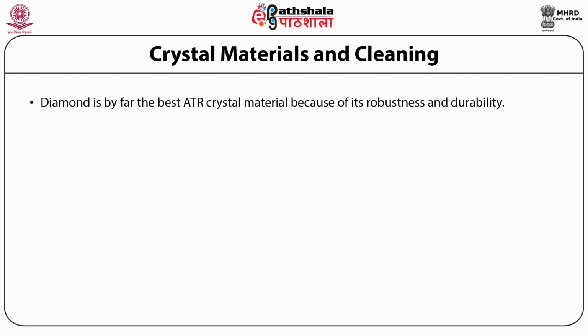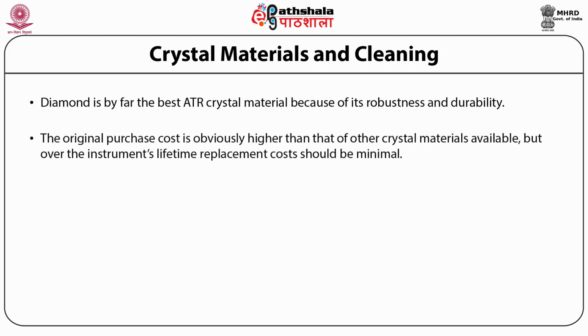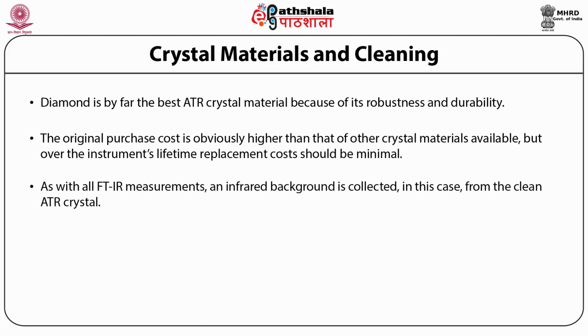Diamond is by far the best ATR crystal material because of its robustness and durability. The original purchase cost is obviously higher than that of other crystal materials available, but over the instrument's lifetime, replacement costs should be minimal. The same cannot be said of zinc selenide or germanium, both of which can scratch or break with improper use.